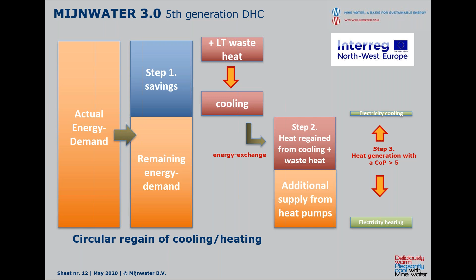Then in this grid, operating at 25 degrees Celsius, we have a very strong source for heat pumps, so we can get very good COPs of heat pumps, given this heat demand and cooling demand. So we actually bring down the 20,000 kilowatt hours original demand through several steps back to maybe 2,000 kilowatt hours electricity. That's an amount of electricity we can deal with in cities, and we have enough roof area to make the 2,000 kilowatt hours from solar panels and other green sources, but we could never do the 20,000 kilowatt hours.